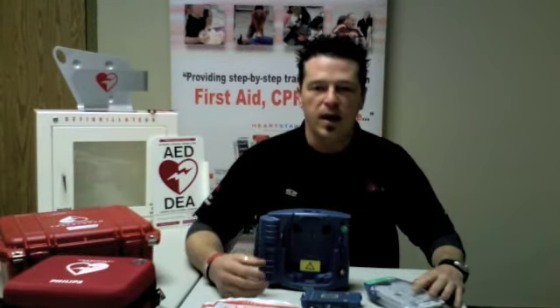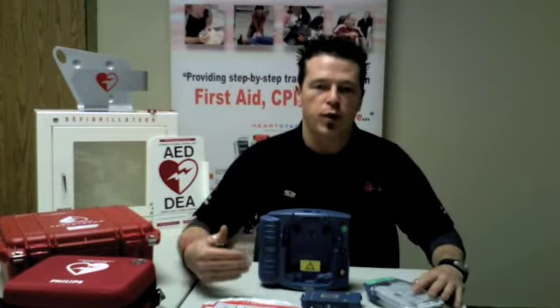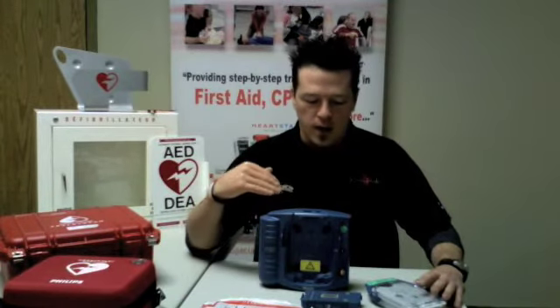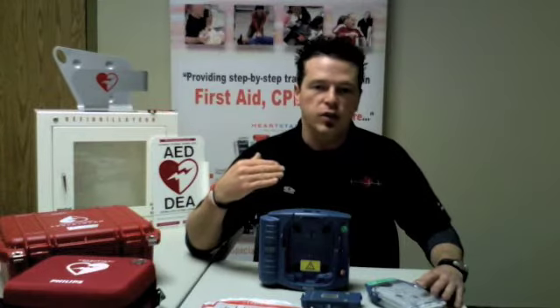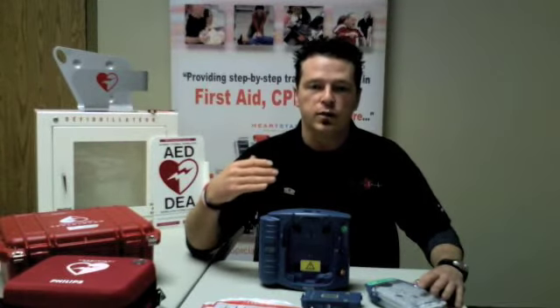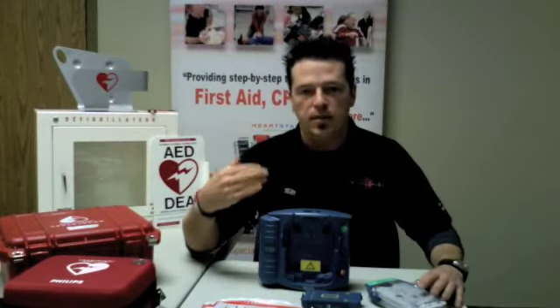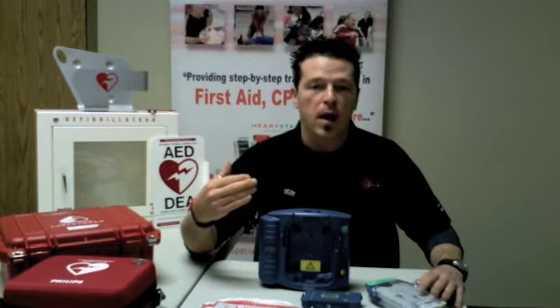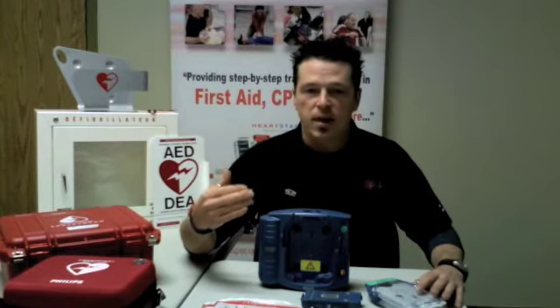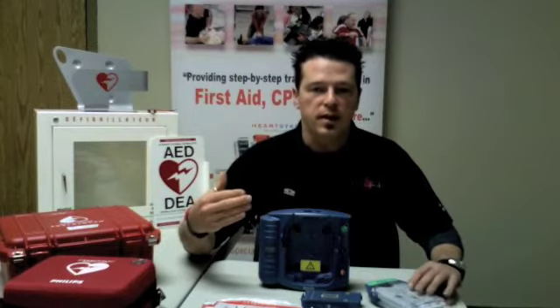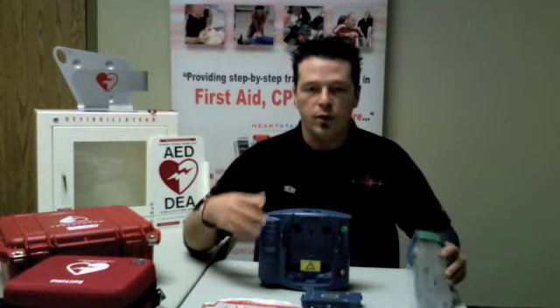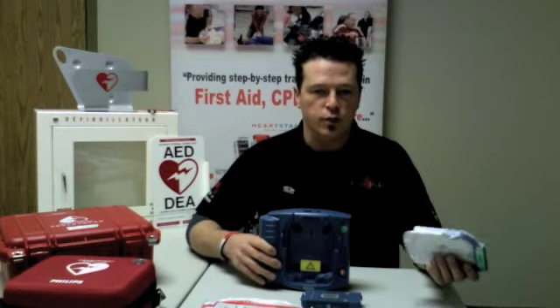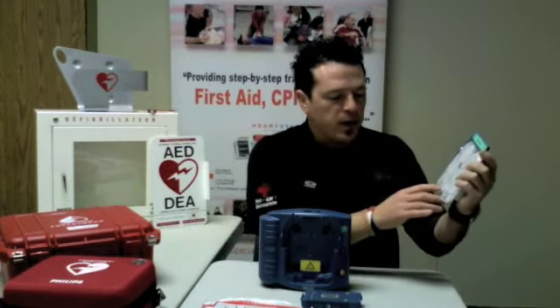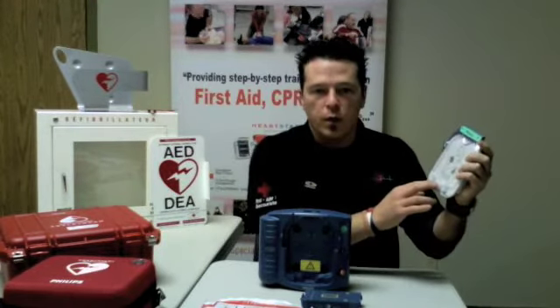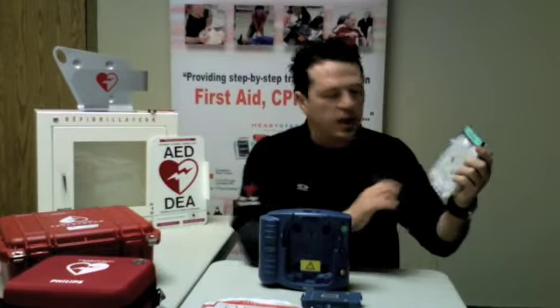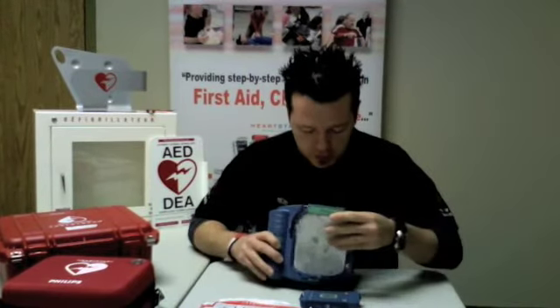By putting the battery back in, the machine will start to initiate the actual diagnostic on itself to make sure that it's in working order. It does it automatically, but if it's a company policy to do this every month, every 6 months, again, for you to decide, all it would require for you to do would be to take out the electrode pads, make sure that the expiry date is within the 2-year window.